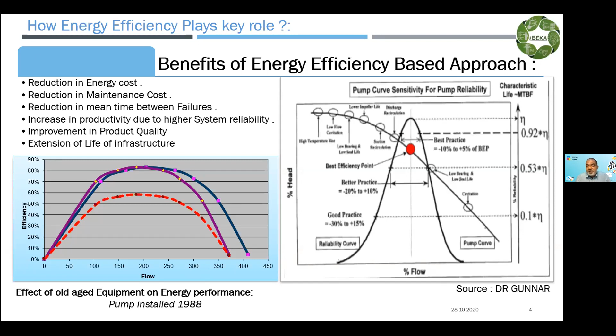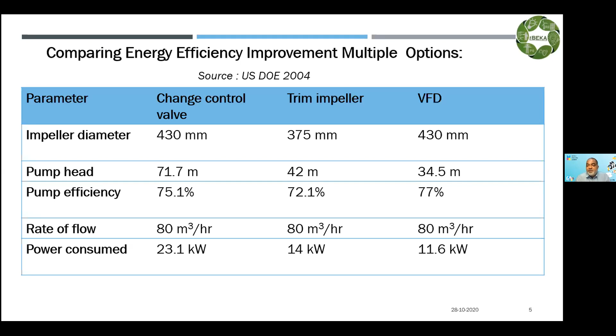There were three energy conservation opportunities: changing the control valve, trimming the impeller, and use of VFD. All three cases were studied in detail, and finally the VFD provided the maximum saving. So the holistic approach allows us to select the VFD, which provides the best ROI, so our investment goes in the right direction and we don't need repeated investment to achieve savings.